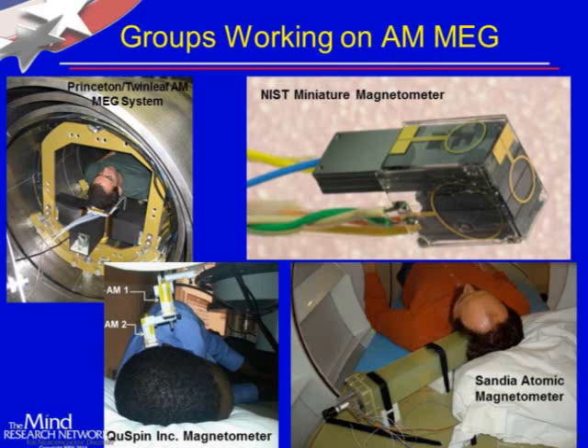My former group at the National Institute of Standards and Technology has probably built the smallest magnetometer that people are using for MEG, about a centimeter on the side. And then this is our device here, a little bit bigger than, say, this device and this device. But what we're trying to do with this single larger device is have four individual channels, so we can have a single module that measures the field at four spatially separated points inside the sensor.